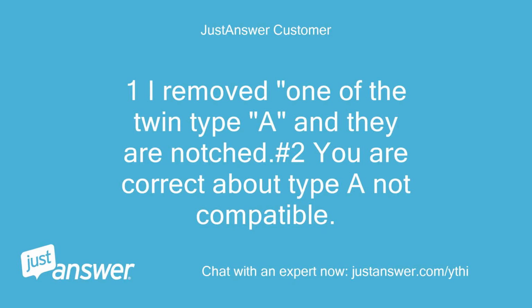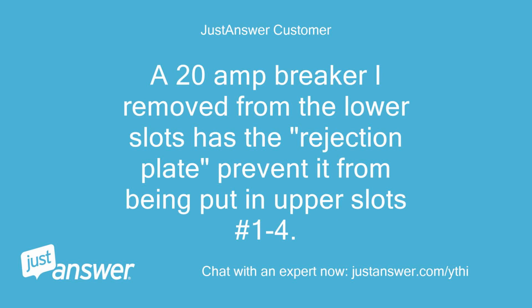1. I removed one of the twin type A and they are notched. 2. You are correct about type A not compatible. A 20 amp breaker I removed from the lower slots has the rejection plate prevent it from being put in upper slots 1 to 4.